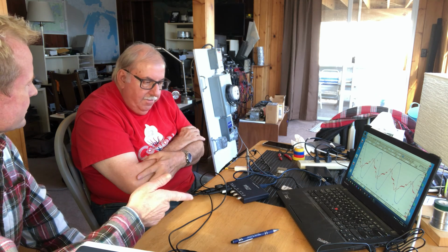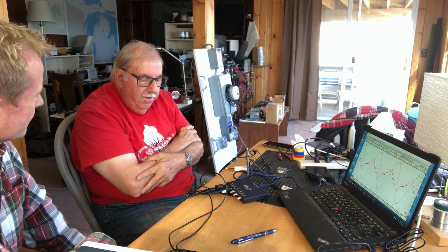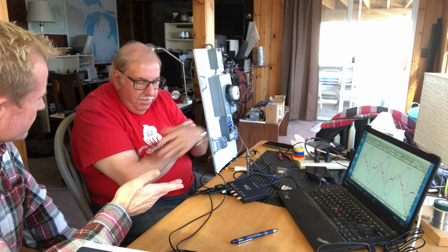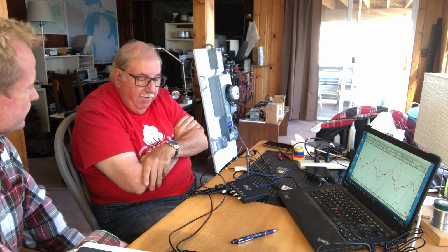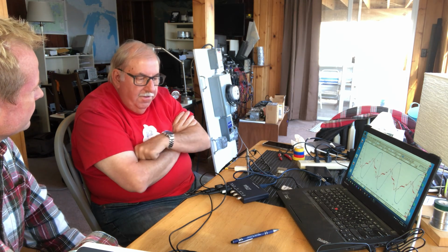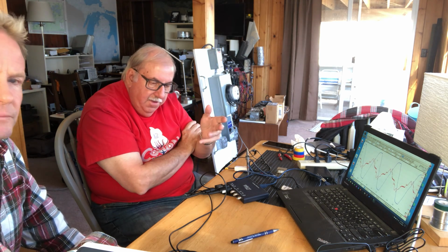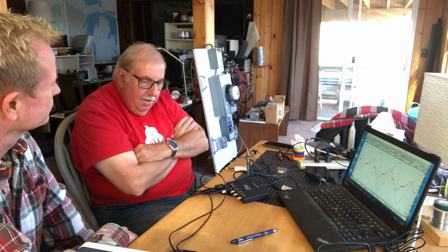And what actually caused that new system to be dirty? The power supplies were so dirty, they were putting out noise. Is that because you're on different voltages, or because? Because it was switching from AC to DC, and the noise factor was really high on the power lines, and so it was basically corrupting the entire environment. So the sensors couldn't get a clean signal because of this disruption.